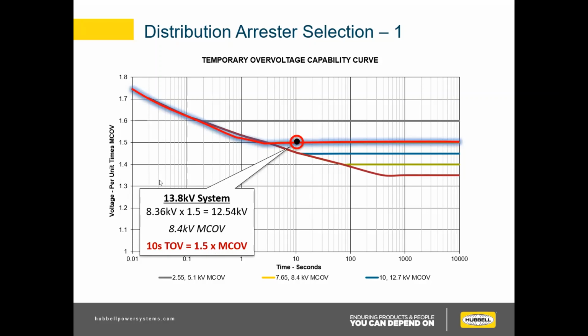The arrestor is designed to handle it. Arrestors are designed to withstand a given amount of TOV, but we need to make sure it's within those means. So here, 1.5 per unit, followed over here to 10 seconds. We're right on this line, and we know that this arrestor will be able to handle that TOV and should not cause any problems.